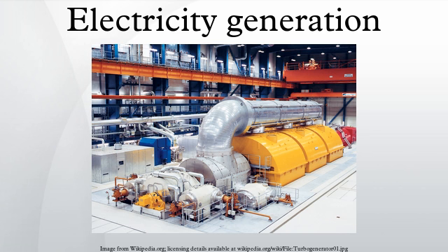Water consumption. Most large-scale thermoelectric power stations consume considerable amounts of water for cooling purposes, and boiler water make up. 1 liter per kilowatt-hour for once-through, and 1.7 liters per kilowatt-hour for cooling tower cooling. Water abstraction for cooling water accounts for about 40% of European total water abstraction, although most of this water is returned to its source, albeit slightly warmer.